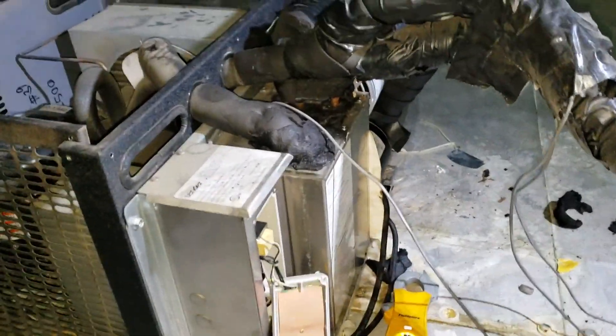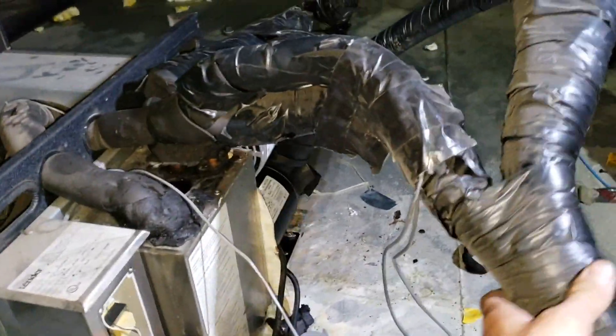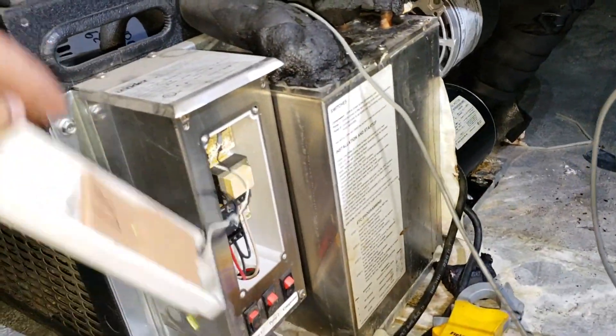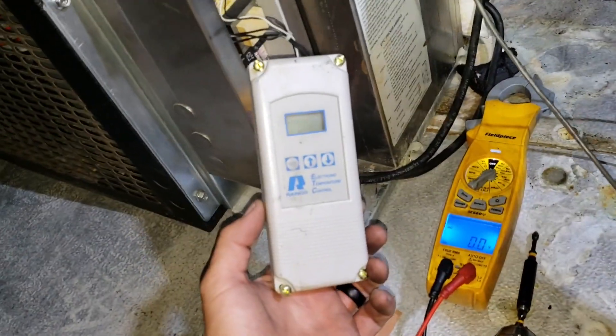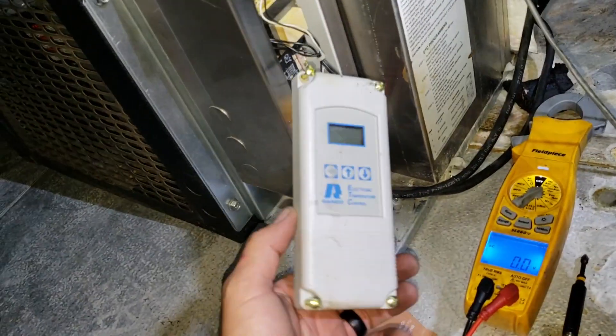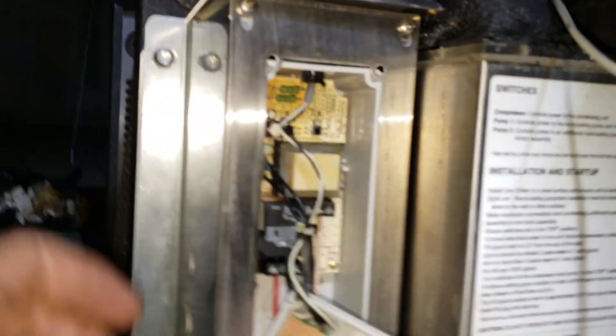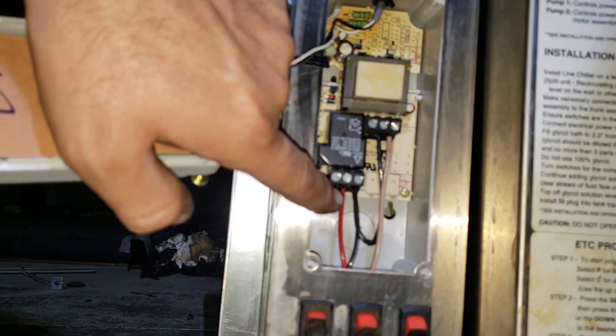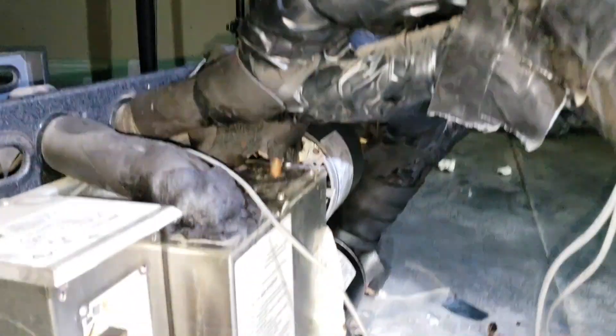I went ahead and repositioned the unit — I was lucky because it's just sitting up here and these are flexible glycol lines. I twisted the unit around to get better access to the control. This is a Ranco ETC-111000 electronic temperature controller, and it's multi-volt — it can do 115 or 208 volts. Inside you can see a set of power contacts on one side and your system contacts on the other.